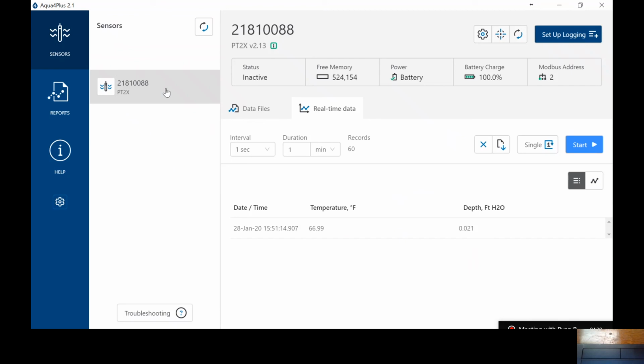So to sum it up, we found our sensor. We went into our settings. We set our date and time. We changed it to full batteries. We went to calibration. We set it to 0 and applied it.